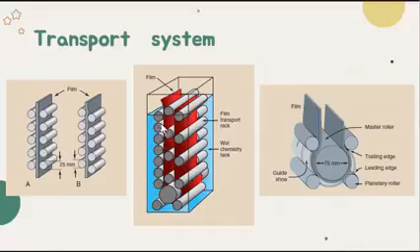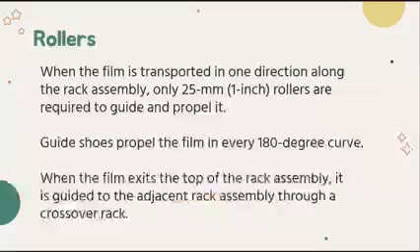Okay? Without the guide shoes in our processor, there is a possibility that the film will get inserted in here, and it will result in longer exposure to processing chemicals. So that is why we have our guide shoes, so that the transport of the film stays within this area and it will guide it into this area only. So nothing goes in here, nothing goes in here, nothing goes in here. Okay, that is the function of your guide shoes.